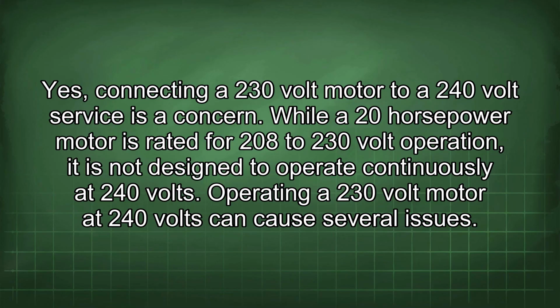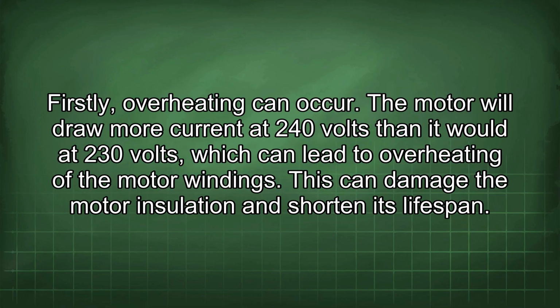Yes, connecting a 230-volt motor to a 240-volt service is a concern. While a 20 horsepower motor is rated for 208 to 230 volt operation, it is not designed to operate continuously at 240 volts. Operating a 230 volt motor at 240 volts can cause several issues. Firstly, overheating can occur. The motor will draw more current at 240 volts than it would at 230 volts, which can lead to overheating of the motor windings. This can damage the motor insulation and shorten its lifespan.